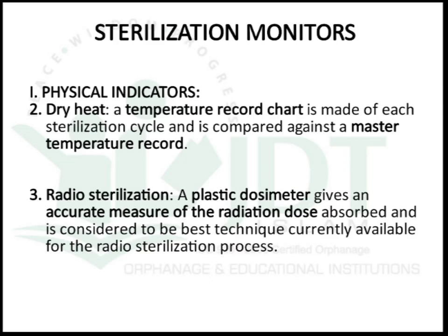For physical indicators in dry heat sterilization, a master temperature record is prepared as part of validation. The temperature record chart made for each sterilization cycle is compared with the master temperature record, and if there is any change in temperature it must be adjusted to control the sterilization process.